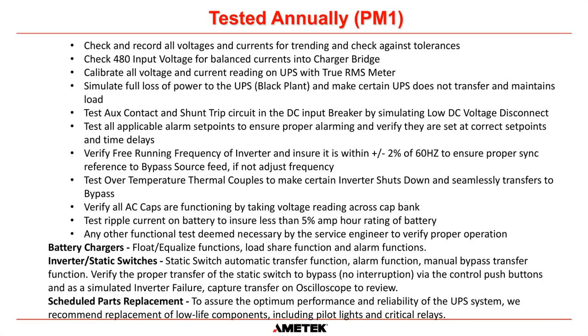We also simulate a full loss of power to the UPS and make sure that the UPS does not transfer and maintains your load circuit. So basically, we will switch off the AC input and we will switch off the bypass input if the plant gives us permission to do this. And we will run on batteries and inverter only and make sure that the system does it correctly. Now, we'll be able to do this with a system in remote bypass position without effectively jeopardizing the loads. And we just want to make sure that the system, if all power went off, maintains the load circuits through the battery and the inverter.